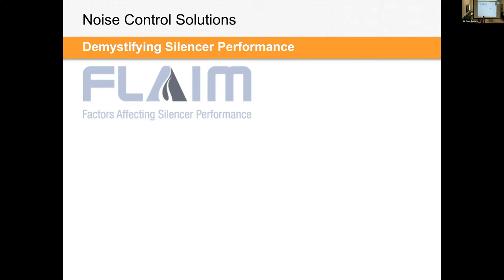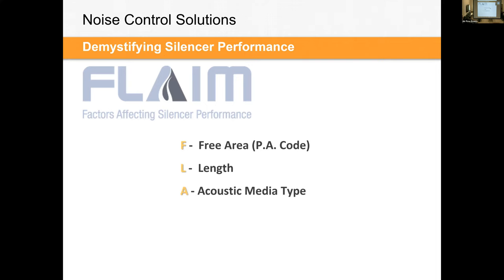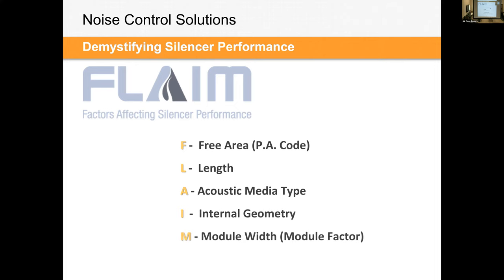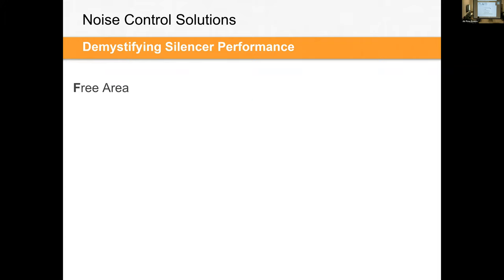So let's look at this FLAIM crazy acronym I came up with and try to understand the factors affecting silencer performance. The F is free area, or open free area, or free open area, and we use the PA code to describe that. I'll explain what that means in more detail. L is the length. A is the acoustic media, so the type of fill or acoustic media. I is the internal geometry. And then M is the module width or the module factor. Some of these might be a little bit convoluted. What is PA code or module factor? I'll walk through these with you and hopefully you'll leave this with a great understanding.